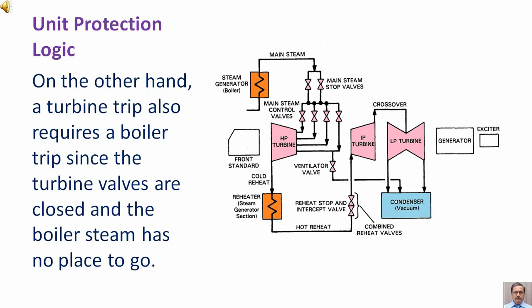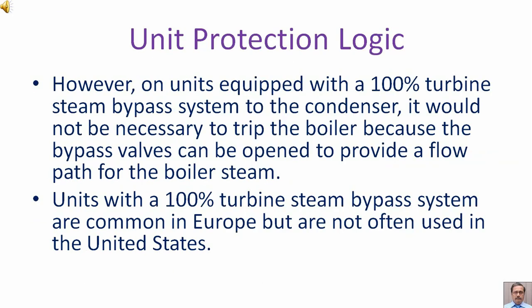On the other hand, a turbine trip also requires a boiler trip, since the turbine valves are closed and the boiler steam has no place to go. However, on units equipped with a 100% turbine steam bypass system to the condenser, it would not be necessary to trip the boiler, because the bypass valves can be opened to provide a flow path for the boiler steam. Units with a 100% turbine steam bypass system are common in Europe but are not often used in the United States.